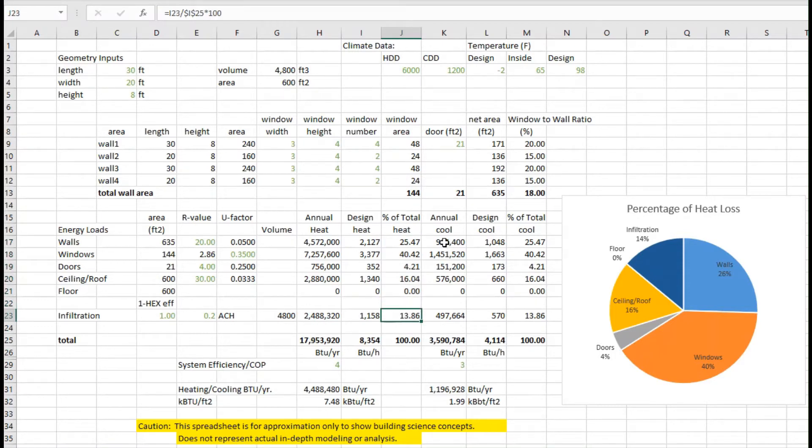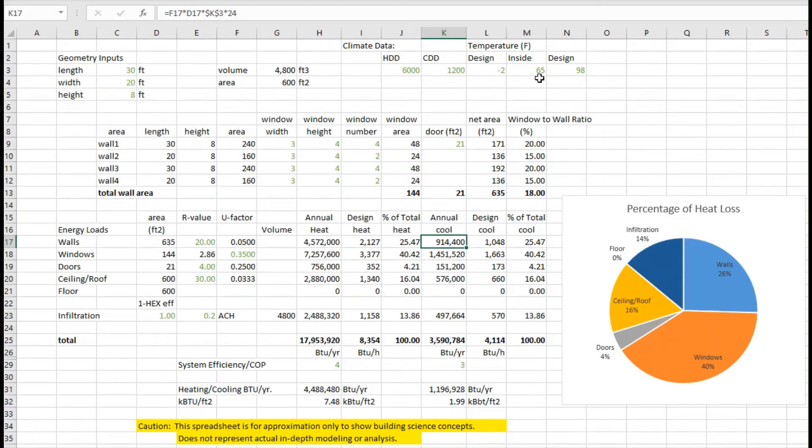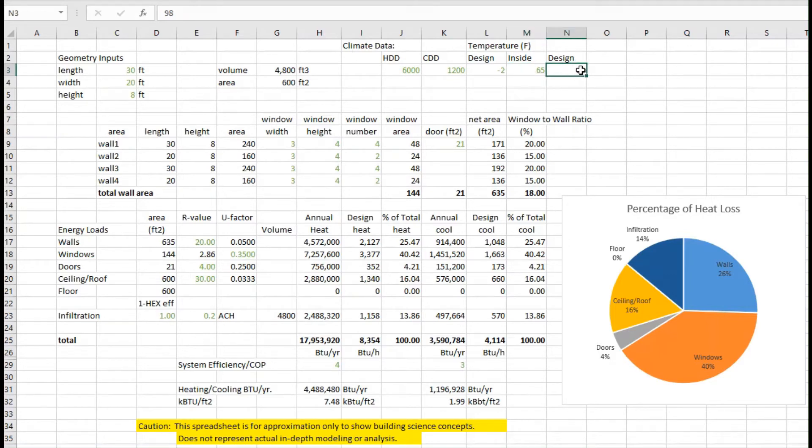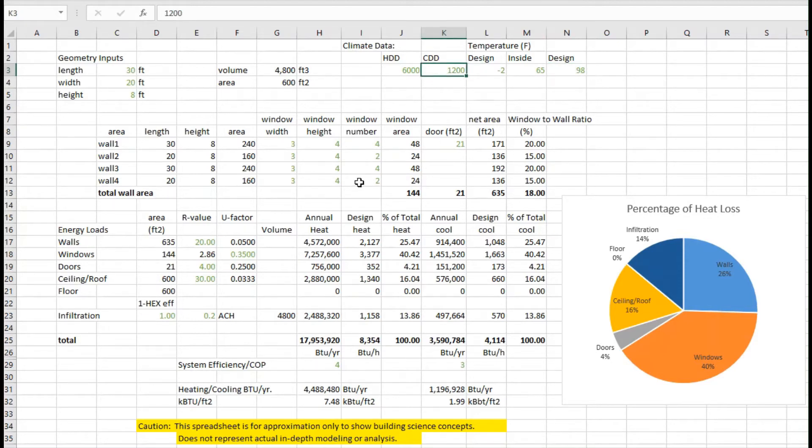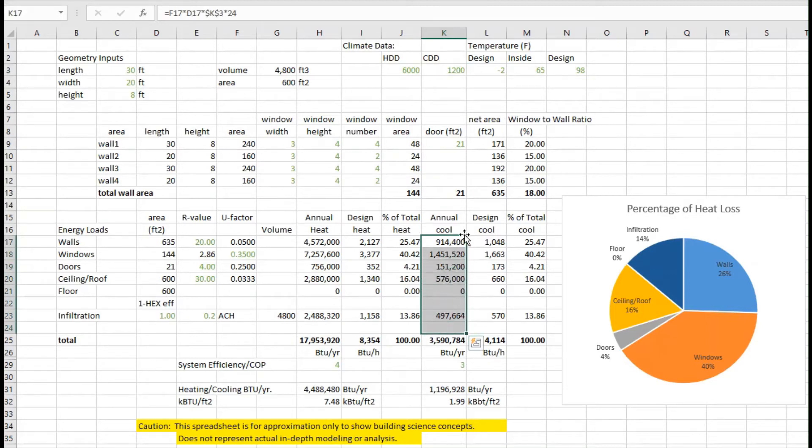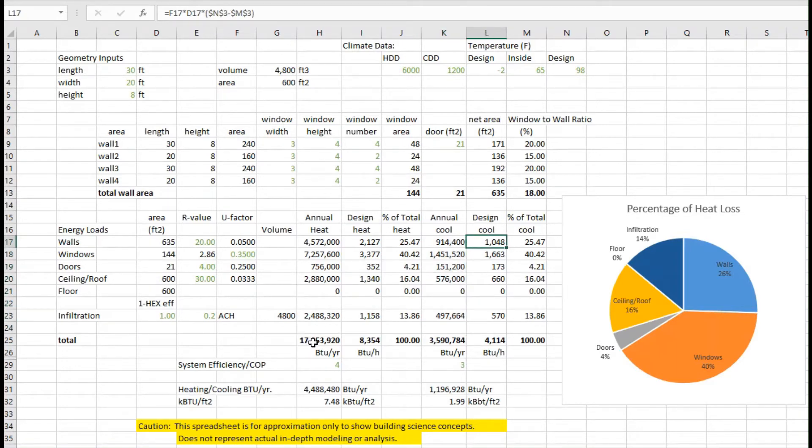I can do the same for the cooling load. In this case remember that humidity may really throw these numbers off, and these are really just an approximation. To kind of approximate some of the humidity concerns, we can pick an inside temperature that's a little cooler than you'd really keep it. The design let's say is 98 degrees Fahrenheit outside, I've got 1200 degree days in this particular climate model. So I can calculate the annual amount of cooling, just like I did for heating, and the design cooling, and again the percentage.